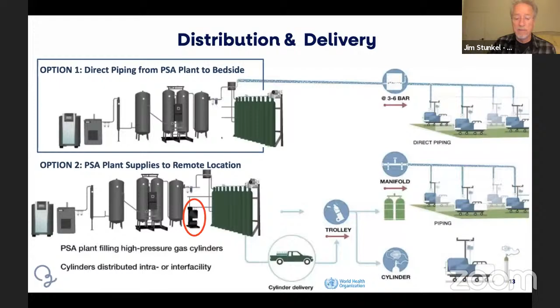That's all right. Option 2 is the PSA supplying a remote location. In this case, the PSA plant may not be on site at the hospital you want to serve, or you may want to serve multiple hospitals. You would fill cylinders using a cylinder filling compressor, shown in the red circle, and then cylinders are delivered by truck or hand trolley to the hospital, either to a remotely located manifold and pipe system, or to the bedside of the patient.